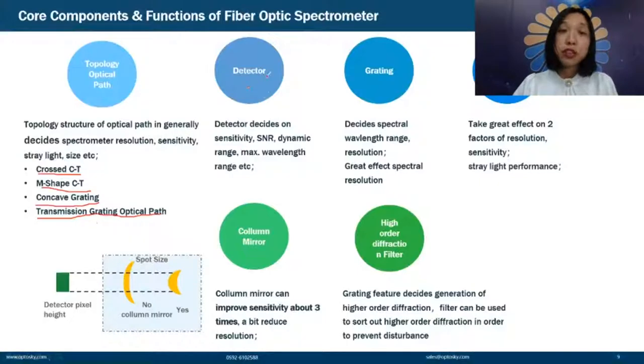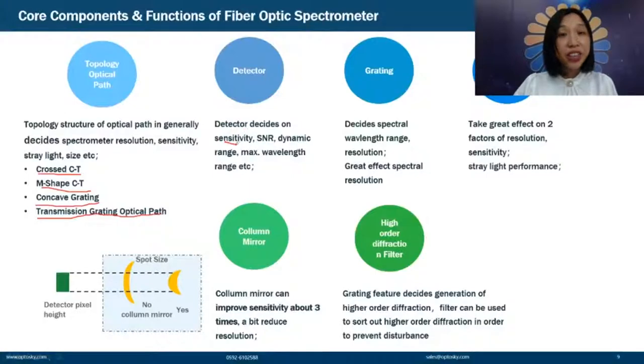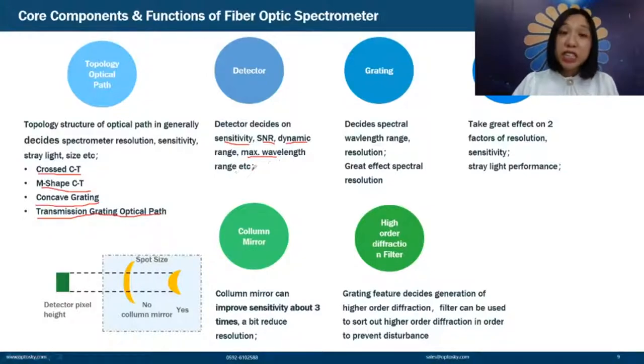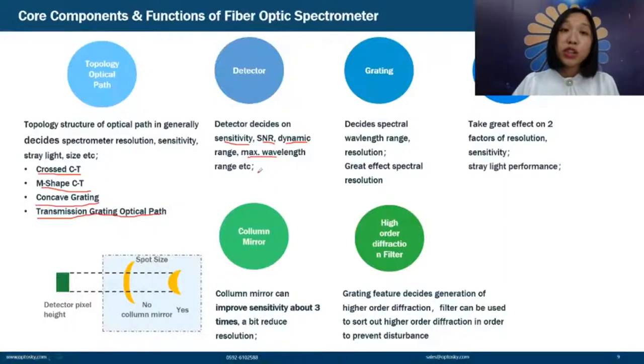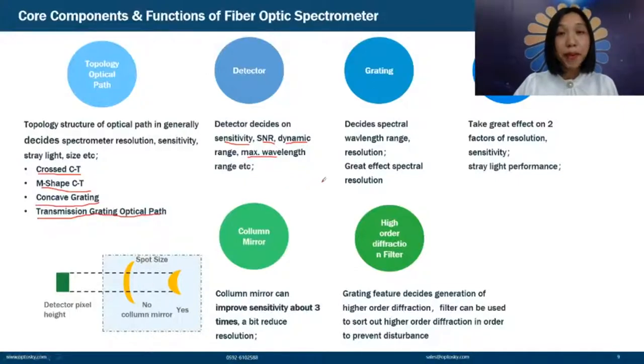Second, we must consider the detector — the most important component affecting spectrometer performance. The detector decides sensitivity, signal-to-noise ratio, dynamic range, and maximum wavelength range. The detector also makes up the main cost of the spectrometer. A cooled detector can cost thousands, while an uncooled one may cost a few hundred dollars.